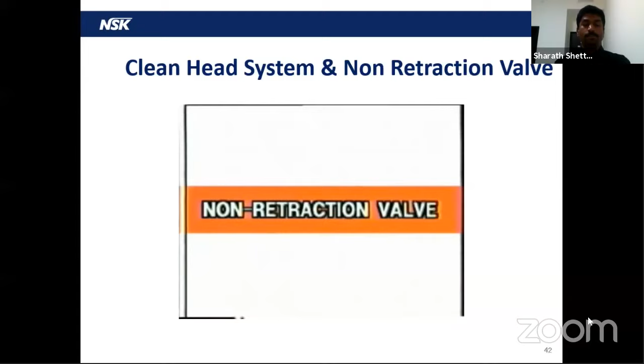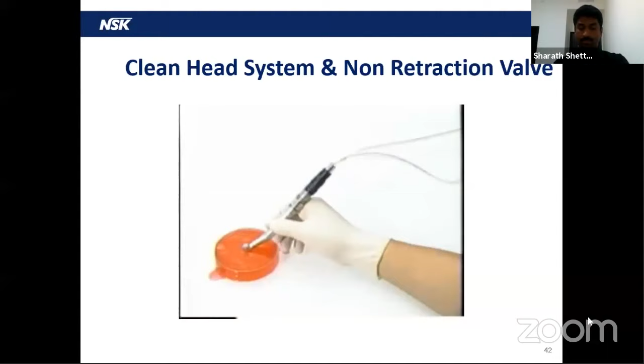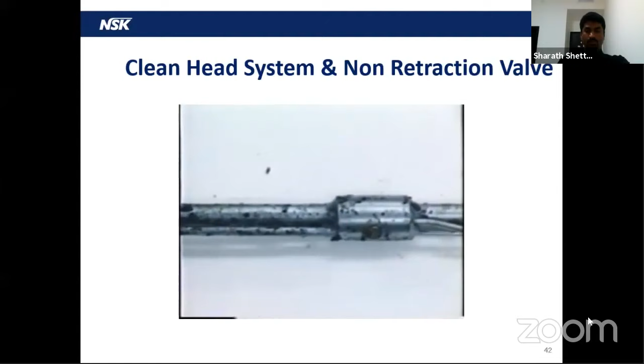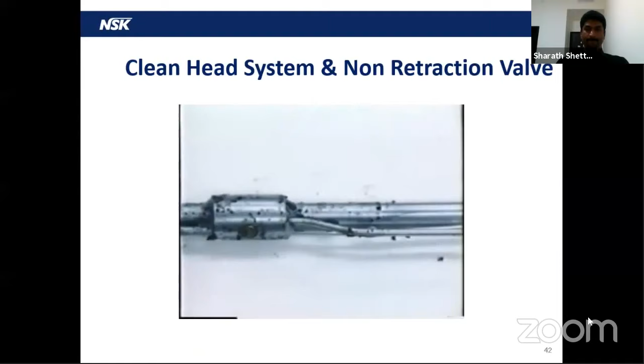Let's look at the non-retraction valve mechanism. Dental units used in most countries have a water retraction system, designed to prevent dripping of water at the head when the handpiece is stopped. This system draws back not only water, but also debris, virus, and other foreign matter into the water pipe. If retracted into the handpiece hose, the contaminated water flows into your next patient's mouth, even if the handpiece was autoclaved. Contaminants and infectants are thus transmitted to the next patient if water retraction is not prevented. In addition, they often cause clogging of the water passage, may cause deterioration of the pipe and hose, and growth of microorganisms was cited at times.